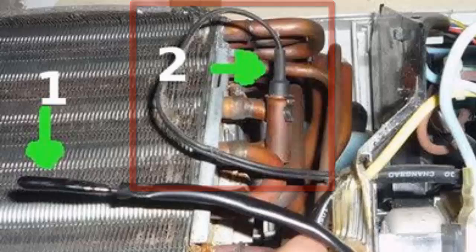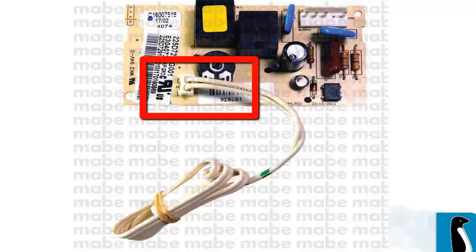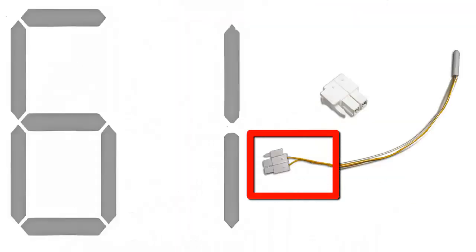3. Check if the thermistor connector is loose on the circuit board. If the sensor has an internal short circuit or if its wire is cut, this error code will be displayed.